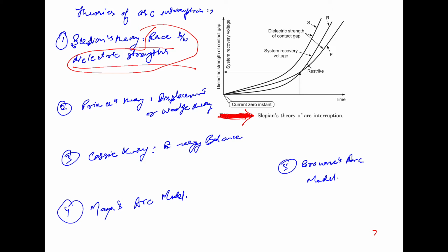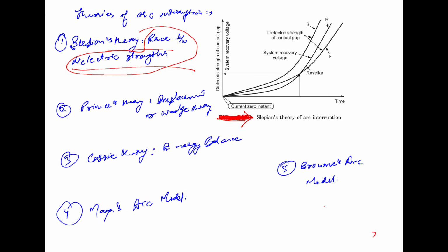Now, the second is the Prince theory. So what is the Prince theory? According to this theory, the circuit is interrupted if the length of the gas discharge path introduced into the arc increases during the interrupting period to such an extent that the recovery voltage is not sufficiently high to produce the breakdown in this path. This theory has now been superseded by other theories.